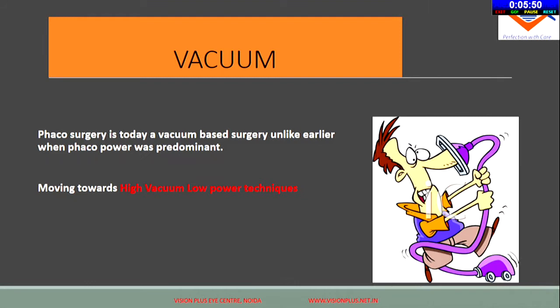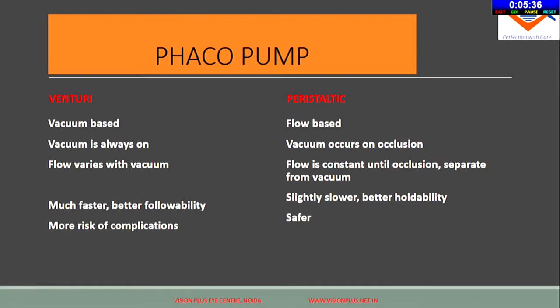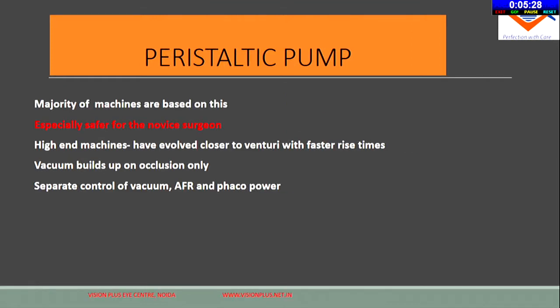Technique has moved from phaco-based surgery more toward vacuum-based surgery. We need machines that can give higher vacuum without causing surge. You have either venturi-based systems or peristaltic-based systems. The peristaltic pump is usually a safer option and the majority of machines are based on this. Higher-end machines have evolved closer to a venturi system where the rise time is very rapid, and vacuum builds up only on occlusion, so it is much safer.